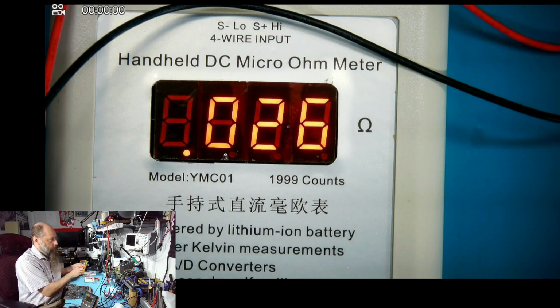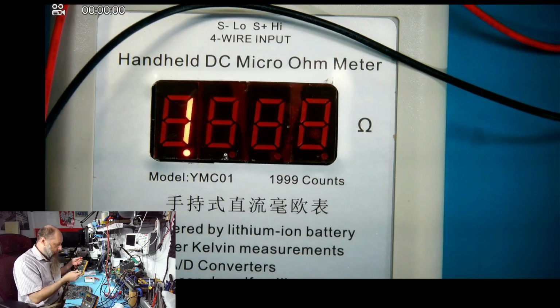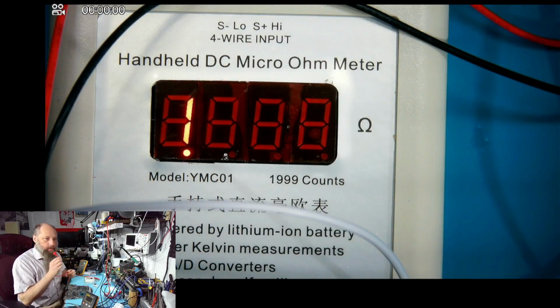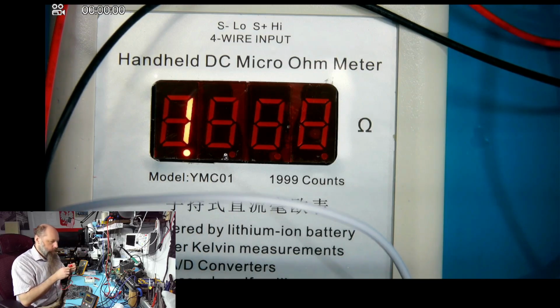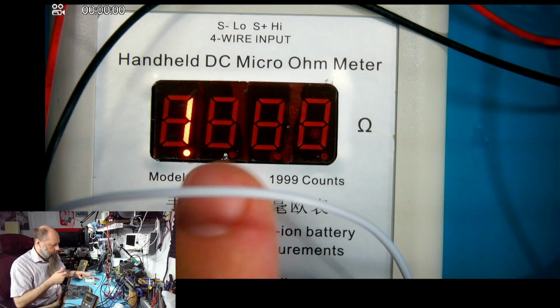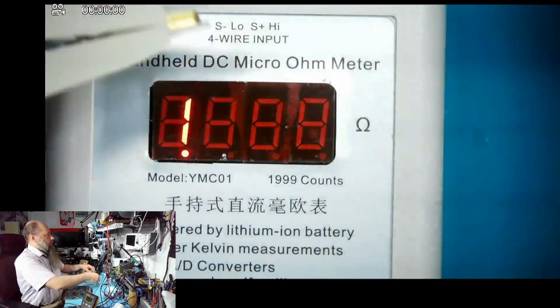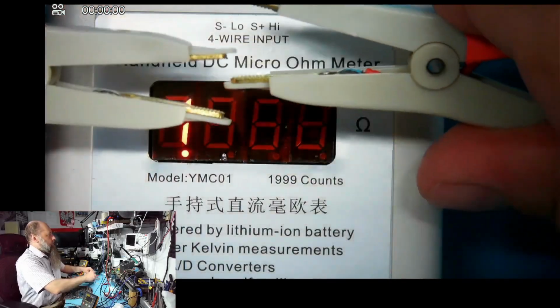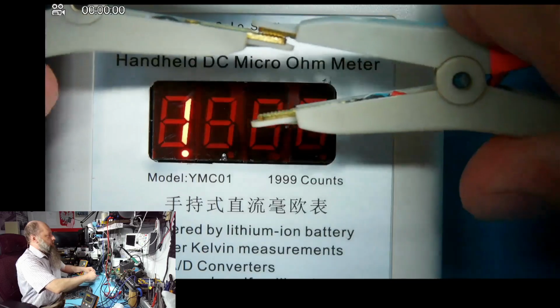And you can see it's relatively stable. I'm holding it with my hand, so it's kind of fluctuating by 1 milliohm, but that's only because I'm touching it. Which means our actual resistance, no matter what you measure, even if you just short 2 probes, is going to be 25 times 2, so 50 milliohms. If we just touch single wires together, as you can see, nothing happens. Now why does nothing happen?